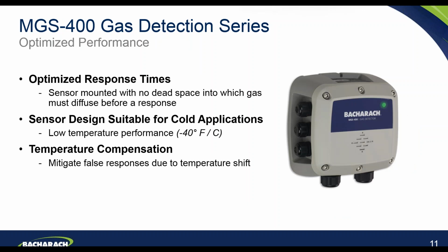From a performance standpoint, the MGS-400, as with all our products at Bacharach, is designed very much with the specific applications that we see and support in the refrigeration and air conditioning industries in mind. So we designed the product to provide optimized performance in those applications and conditions. In particular, the response time is extremely important. It's important that once a gas sensor senses a gas, particularly above an alarm set point, it is very quick to respond to alert personnel or systems in the area to notify them that there is an alarm condition.